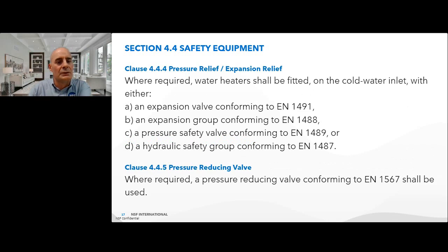Clause 444, pressure relief or expansion relief. Where required, water heaters should be fitted on the cold water inlet with either an expansion valve, an expansion group, a pressure safety valve, or a hydraulic safety group conforming to the listed European standards there. The majority of the cylinders in the UK are supplied with expansion groups, and they contain all the necessary safety devices then.